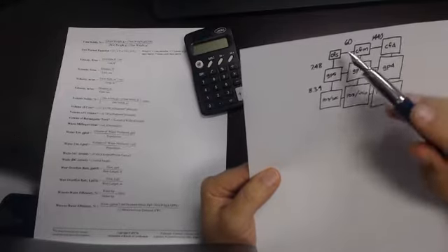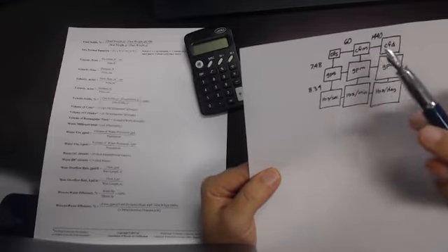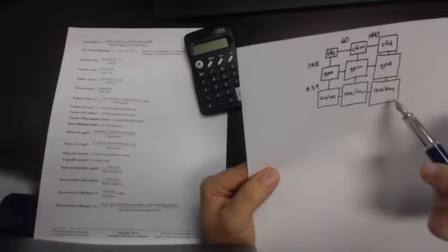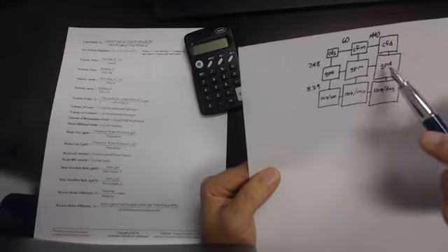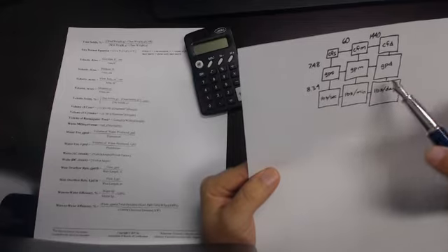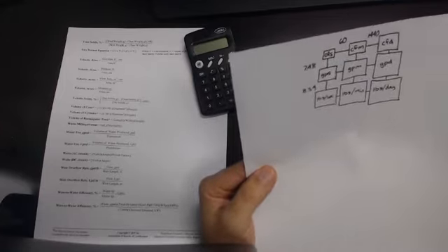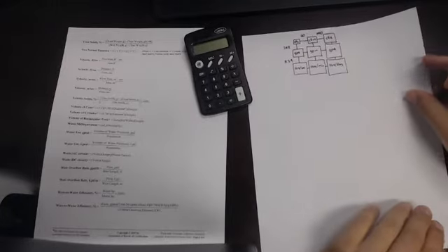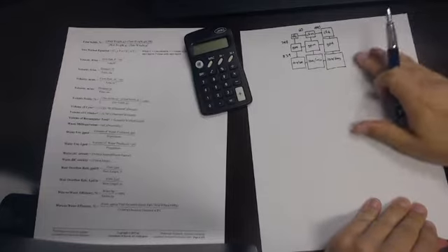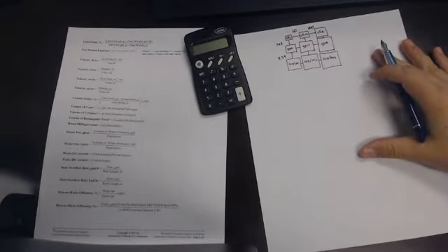And you can do that with any combination of factors that you want to. Cubic foot per second, all the way to pounds per day: you multiply by 60, multiply by 1440, multiply by 7.48, and then multiply by 8.34. And the same backwards with dividing. So this is a really cool tool for helping you with your conversions and making sure that you have the right factor that the question's asking for. So let's get right into some flow calculations.